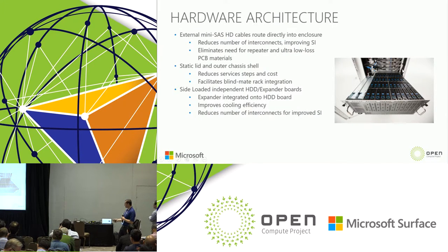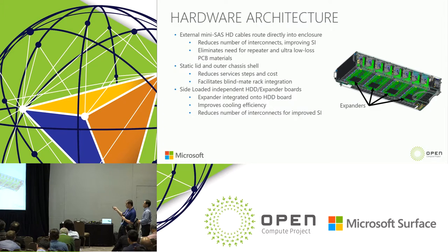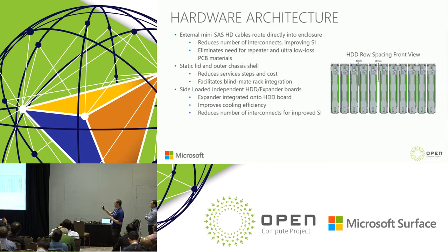The design enabled very simple cable management — the data center doesn't have to deal with external cable arms, it's all done internally in the shell, speeding up rack integration. Also, because we put the SAS expanders on the bottom of the boards, it enabled us to spread the hard drives further apart, which really reduced airflow impedance — that cooling efficiency was important for improving reliability.